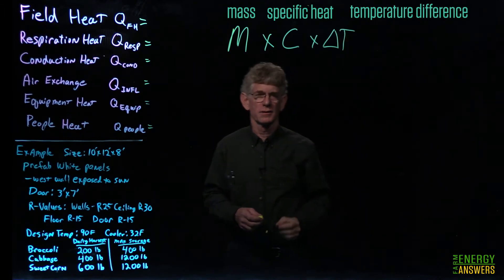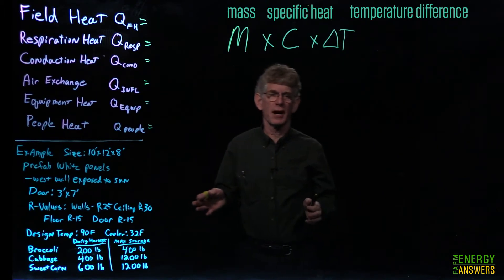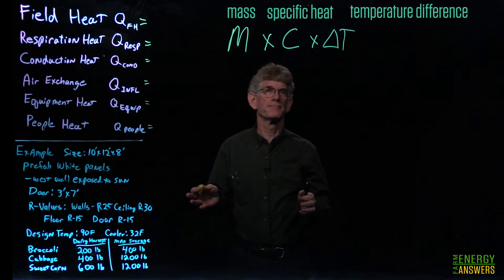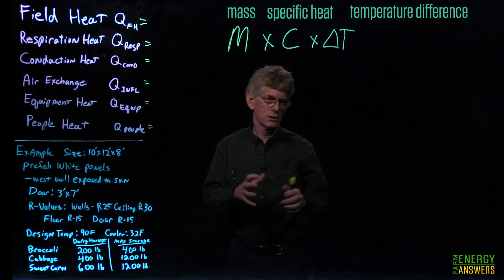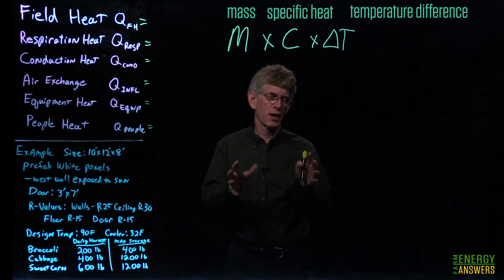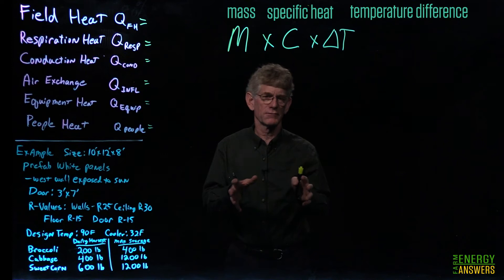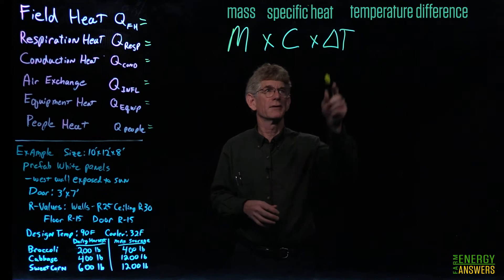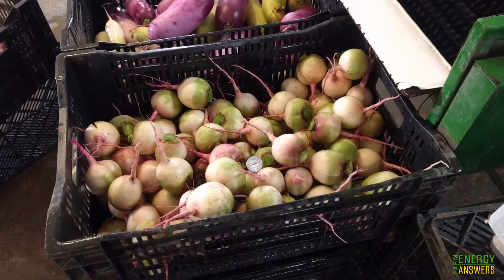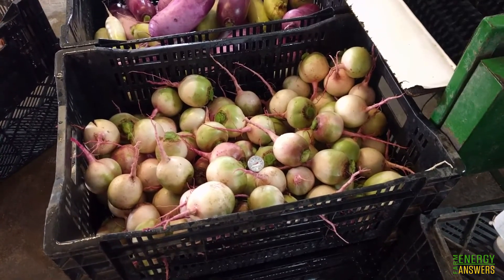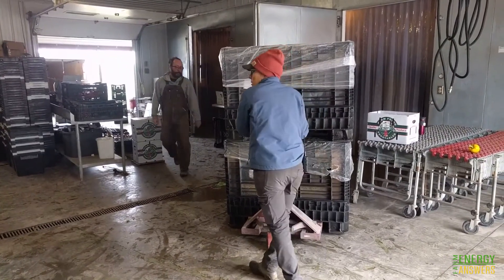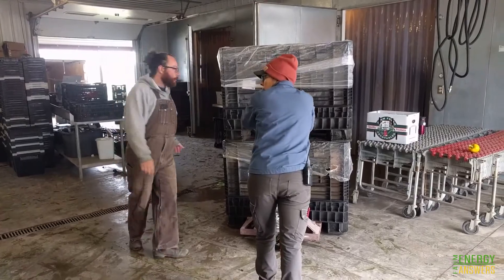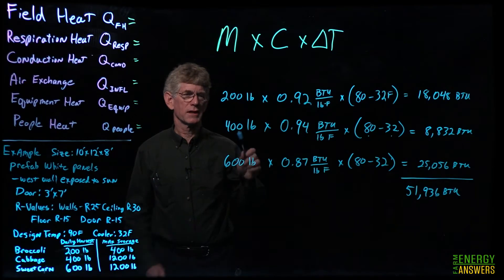Field heat is calculated as: mass × specific heat × temperature difference. The mass is the pounds of product going into the cooler in a 24-hour period. Specific heat is the energy required to reduce the product by one degree Fahrenheit, in units of BTUs per pound per degree Fahrenheit. The temperature difference is between the incoming field temperature and the target cooler temperature. This tends to be the biggest load in a cooler.